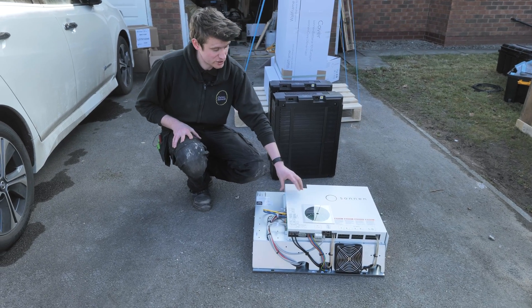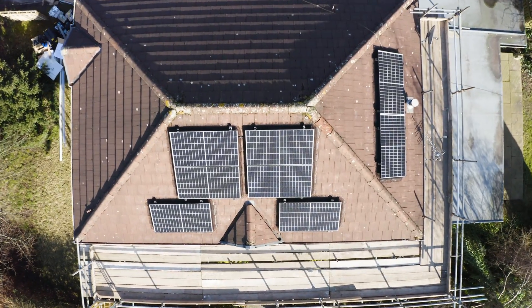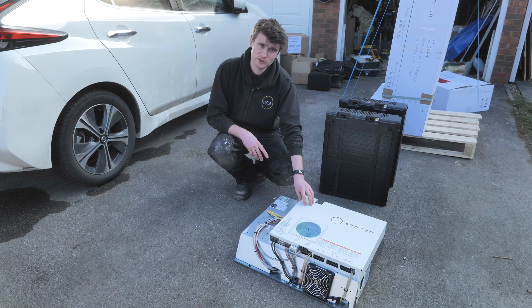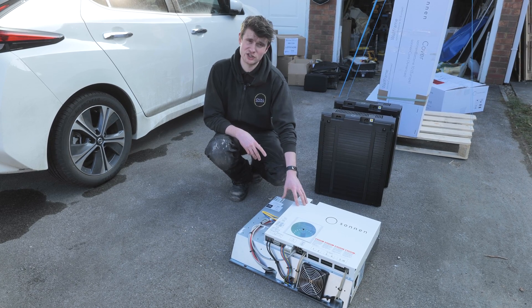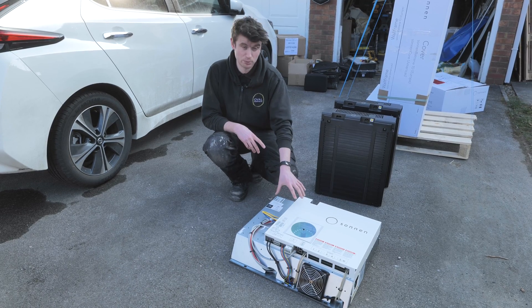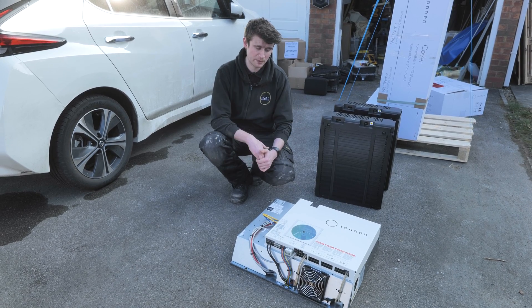For example, if the solar is generating two kilowatts and the home is only using one kilowatt, then this will ask the battery to charge up with one kilowatt of power. If the home is consuming four kilowatts but the solar is producing two kilowatts, then this power unit will ask the battery to discharge with two kilowatts of power. So this part here is really the brain of the system. All of these components go within the cabinet, so it's just one nice-looking flush battery system.